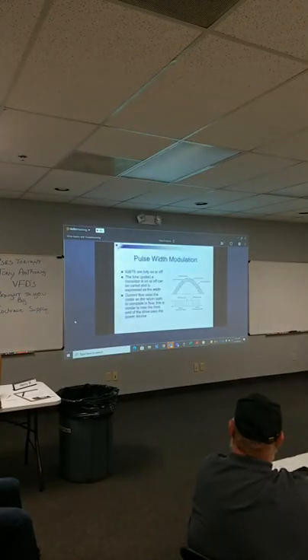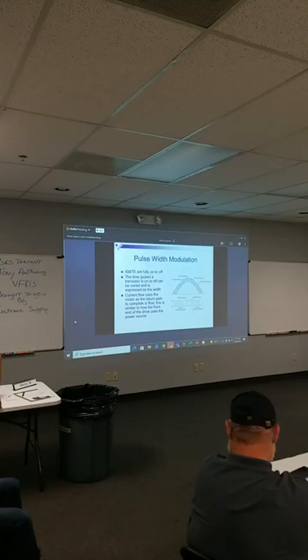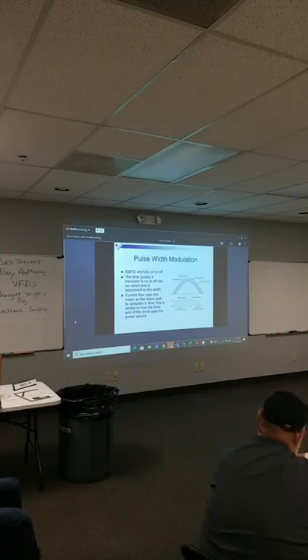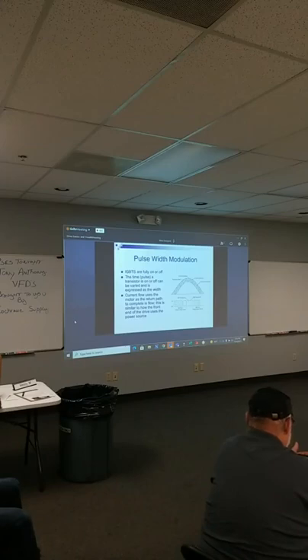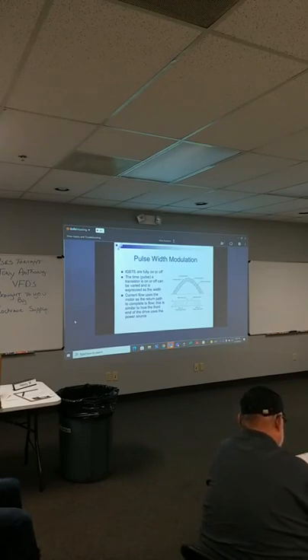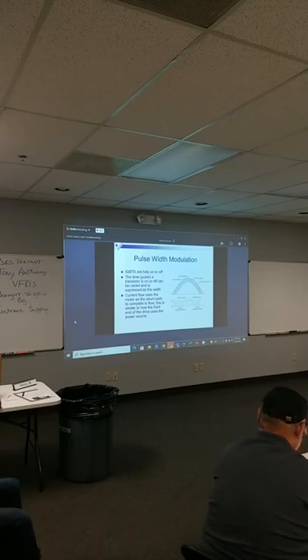All right, so that is the drive. We've got the diode bridge, taking AC, around 1.44 times that, we'll get DC, a DC bus. We've got the capacitors maintaining that DC bus and smoothing it out. And then we've got the fancy switches, the IGBTs, the insulated gate bipolar transistors, turning on and off to create the output to the motor. The pulse width modulation, which you've probably heard in every motor. Now, any questions about that? Any other questions?